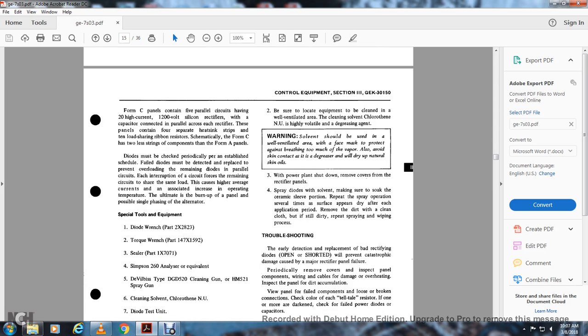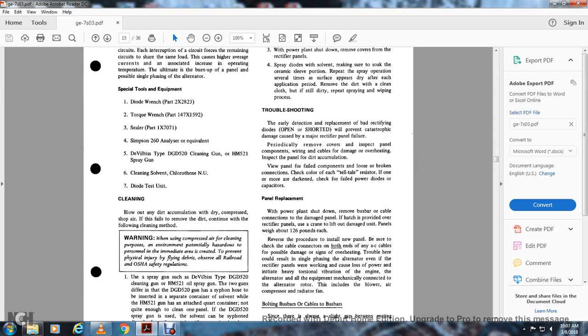Warning: solvent should be used in well ventilated area with a face mask to protect against breathing the vapor. Also avoid skin contact with the solvent, which will remove the natural skin oils. With the power plant shut down, remove the covers of the rectifier panel and spray the diode with solvent, making sure to soak the ceramic sleeve portion, and repeat the spray operation several times until the surface appears dry after each application. Remove the dirt with a clean cloth, and if it's still dirty, repeat the spraying and wiping process.